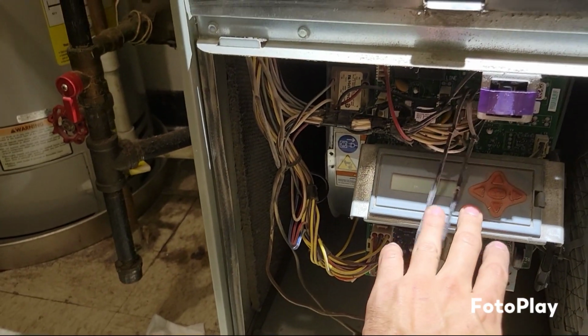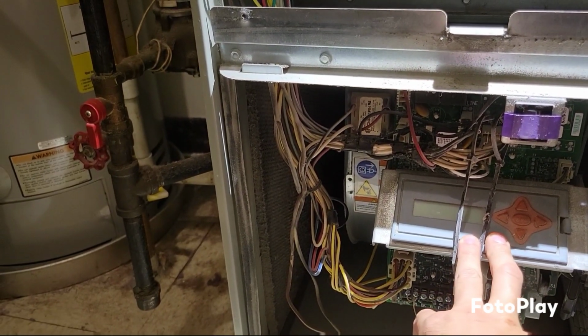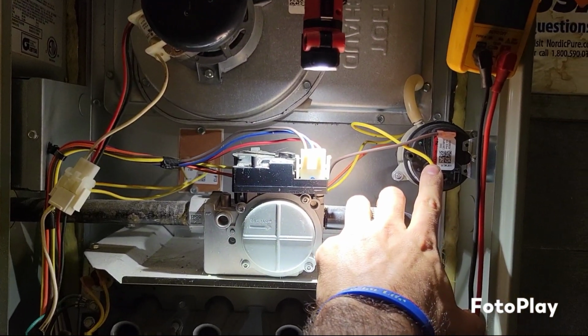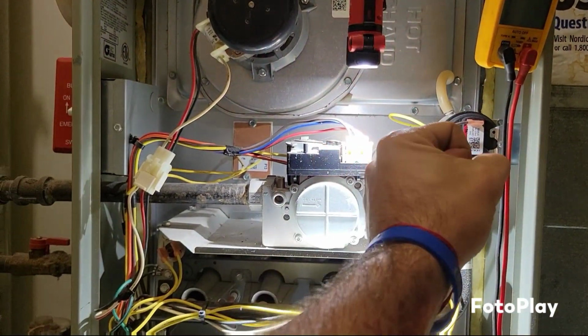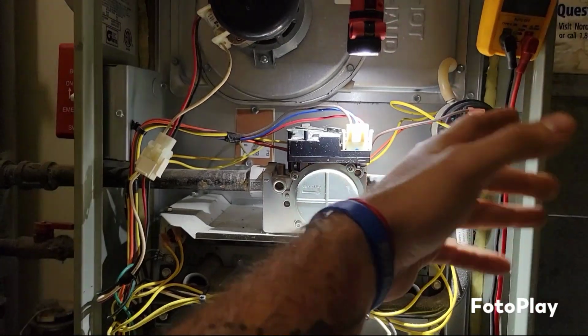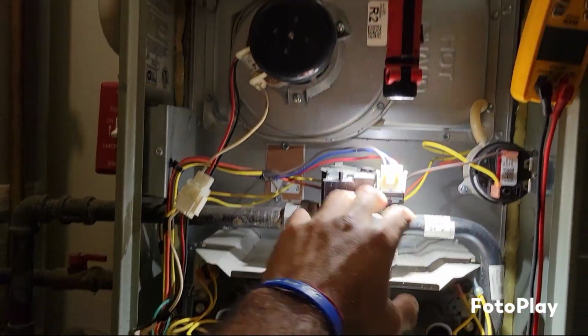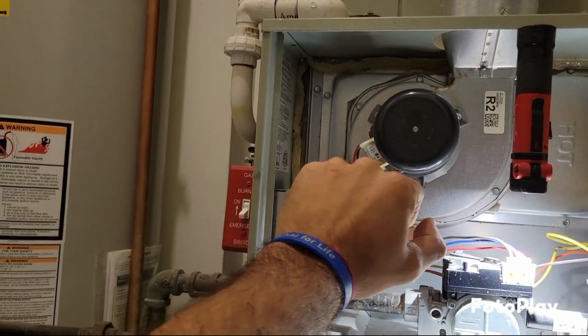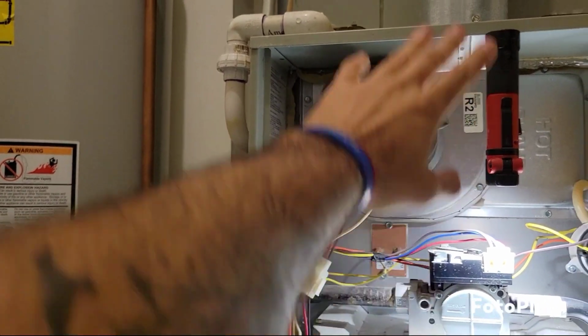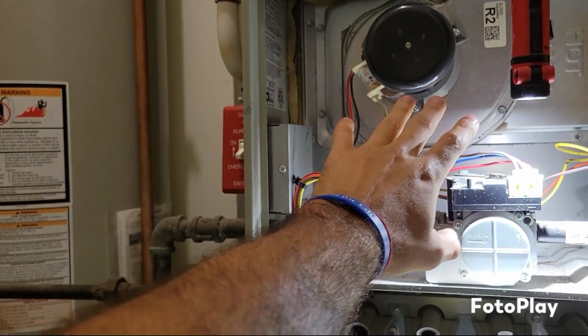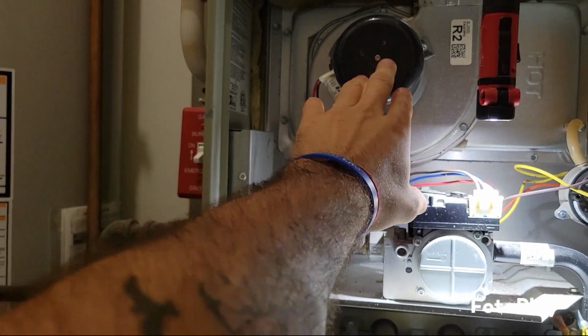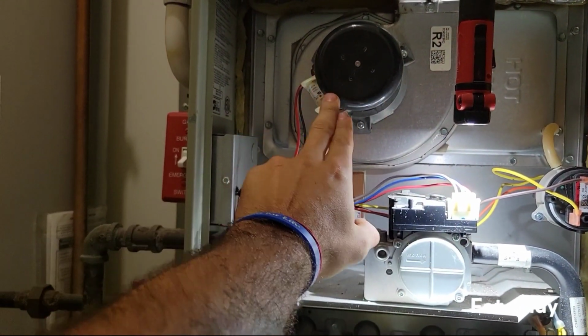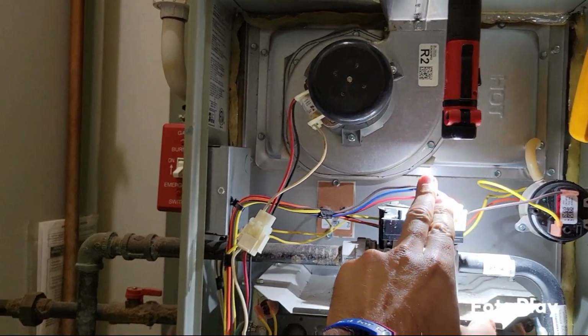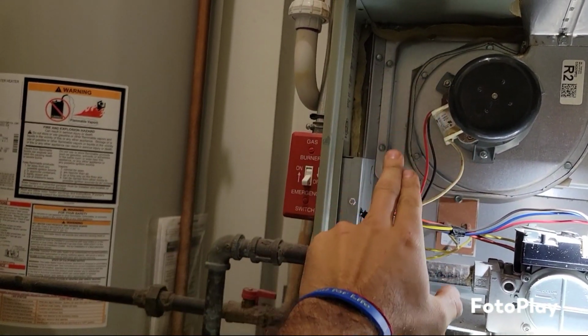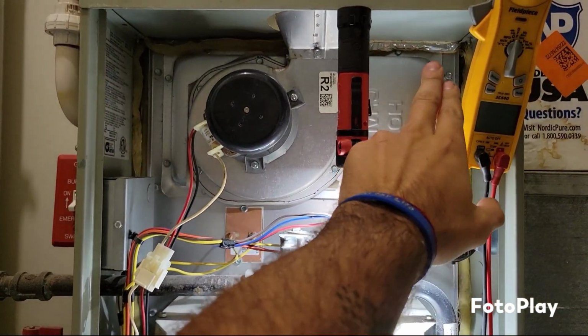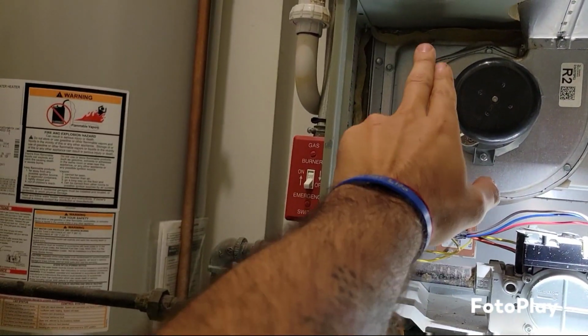So that 3-blink error code says that the pressure switch, which is this guy right here, has failed to close, so it remained open. Now typically during a call for heat, the first thing that kicks on is this guy right here. So this motor starts to spin. As it spins, we are now exhausting the gases out. That spinning cycle is tied in. You look where the motor is located right here on the heat exchanger housing right here. Okay, this is the air box.